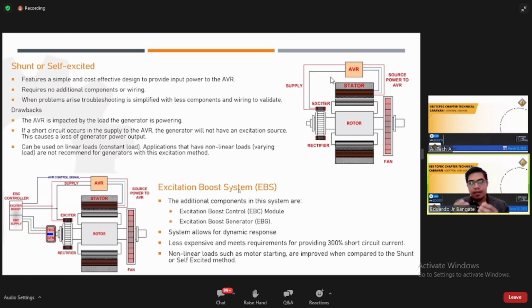But what are the drawbacks? Again, this is very simple, but of course there is an innovation made because there are drawbacks with the previous technology. So what are the drawbacks? The AVR is impacted by the load the generator is powering. Again, I showed earlier how the simple AVR operates, and it reacts immediately according to the loading condition of the generator. It has a triggering voltage. If the triggering voltage is not reached, there's a possibility that it will shut down the generator, so that it will not provide the correct output voltage.